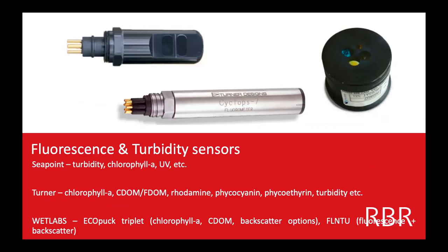We also have different fluorescence and turbidity sensors. We don't manufacture any of these at RBR — they're third-party sensors that we purchase and integrate, but they're very common. The Seapoint turbidity sensor is optical — you can see two different panels here for the light. They also do chlorophyll fluorescence and UV sensors. We have the Turner Cyclops, which is the most common chlorophyll-A sensor that RBR integrates. They also have CDOM, F-DOM, rhodamine, phycocyanin, phycoerythrin, and turbidity — all the same sensor form factor, just changing the light.